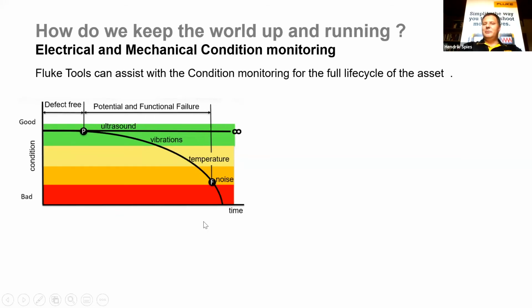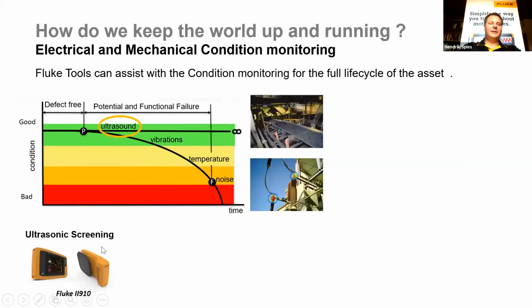So what technologies do we have? So first we've got, you've guessed it, the ultrasonic screening device, the II900 and II910. Remember, sound-based visualization, which is indicated here. This is a conveyor. We've got a bearing on a roller that is actually starting to fail. On the electrical asset here, which is an insulator, we can actually determine that there is some activity there, partial discharge activity.